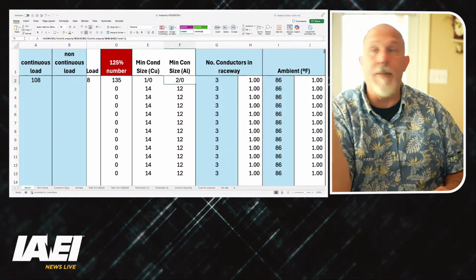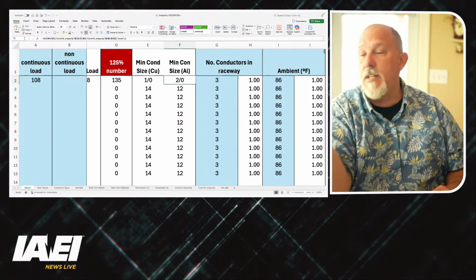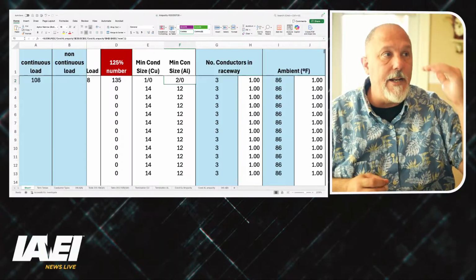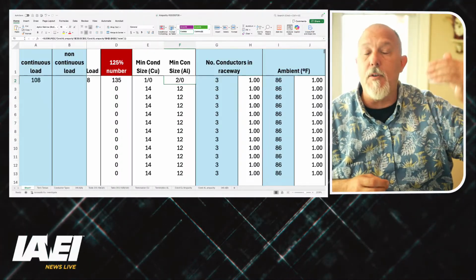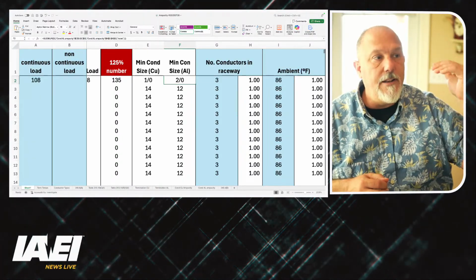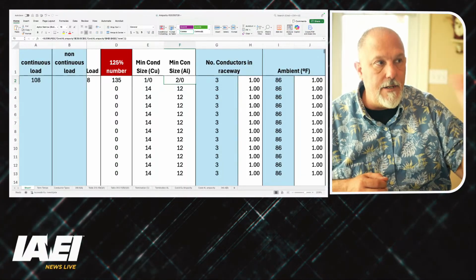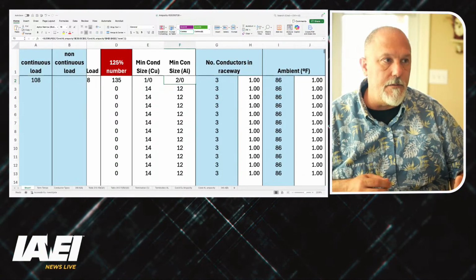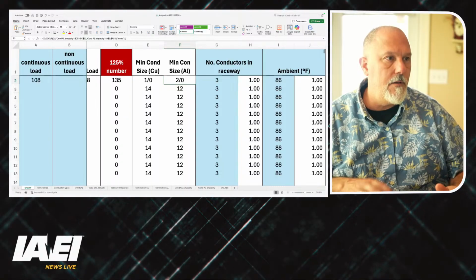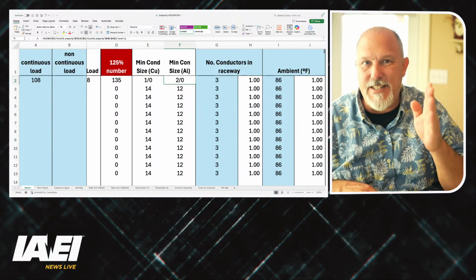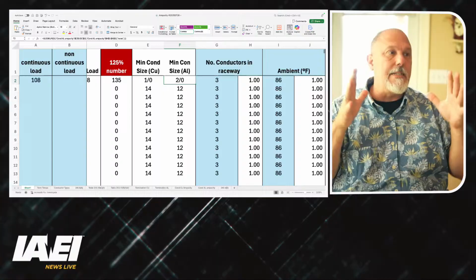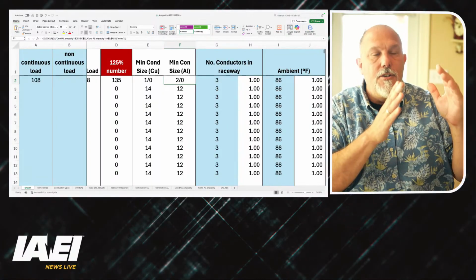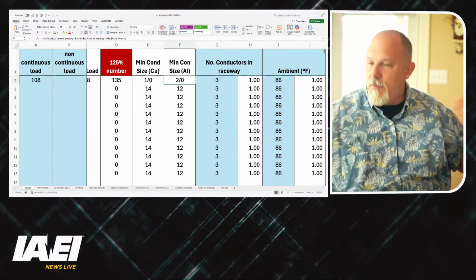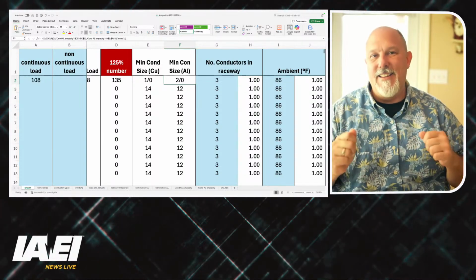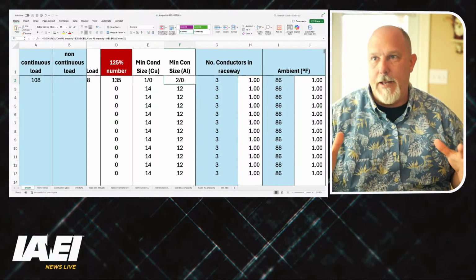Oh yeah, 135 amps, because 125% is 135 amps. So I need 135 amps worth of copper or aluminum conductor, and to get that, I need a 1-aught conductor. Based on the 75 degrees C, I need a 2-aught conductor. I'm looking at the wrong column. All right. Let's go back, because I probably just confused everybody.